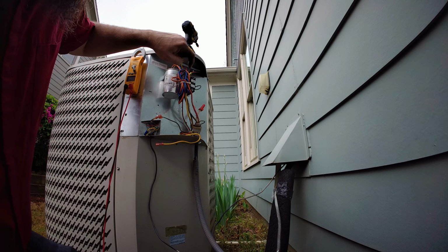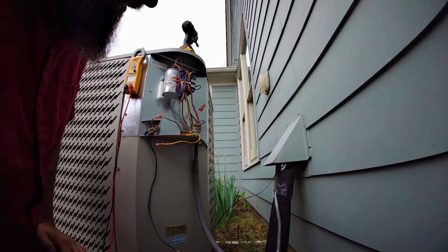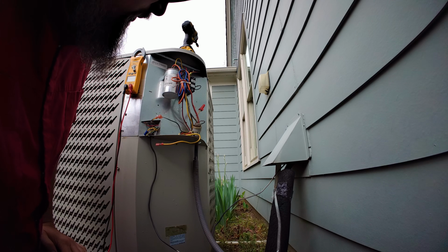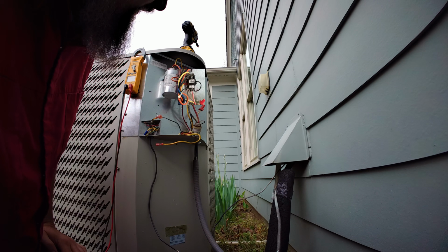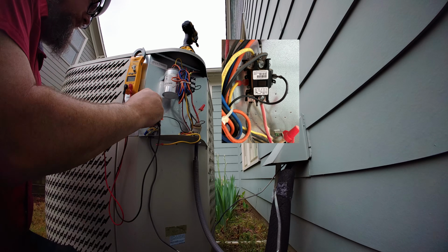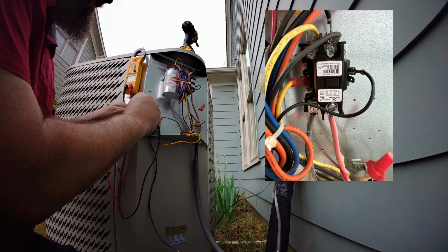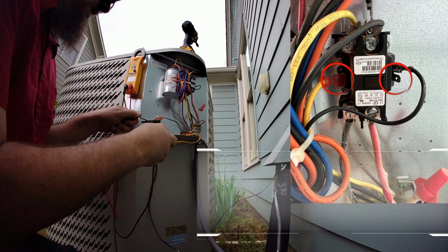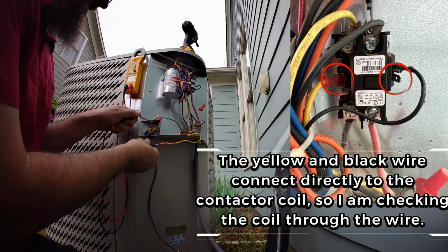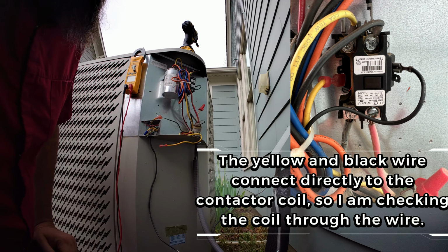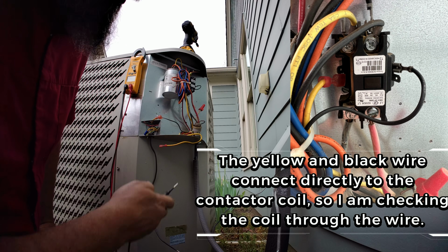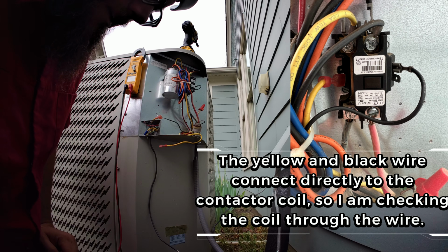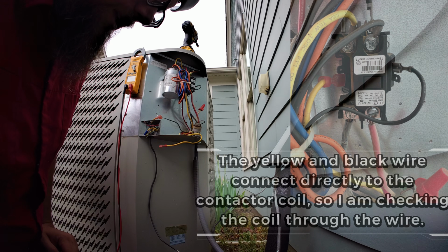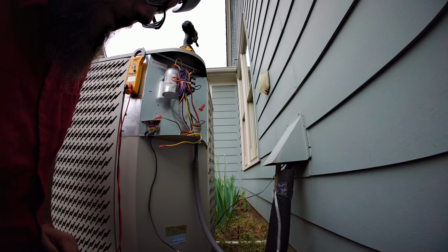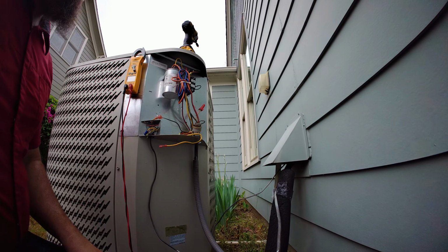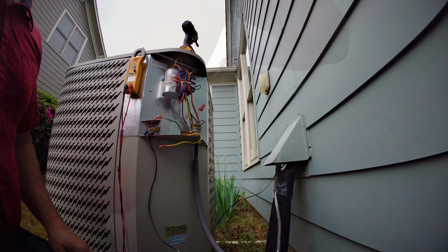My next thought would likely be this contactor is damaged and it's pulling too much amperage. Either that or it is shorted together. So we'll check. Yeah, we have almost a 0 going through the coil on the contactor up there. So that would tell us that our contactor coil is shorted, and that's what's killing our low voltage. So we'll get them a contactor.